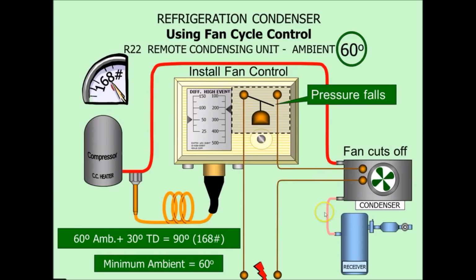And then you'll hook your gauges up to the system and run it during low ambient conditions and watch the pressures and temperatures and the fan cycling and the fan cutting off. You may have to adjust the differential a little bit and the high event just a bit, but this is a very good starting point, and you shouldn't have to make too many adjustments to get it dialed in and get it right. Pretty simple system, easy to install, easy to set up if you understand the high event and differentials.